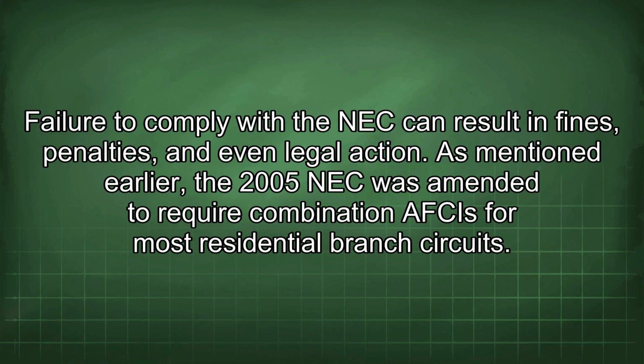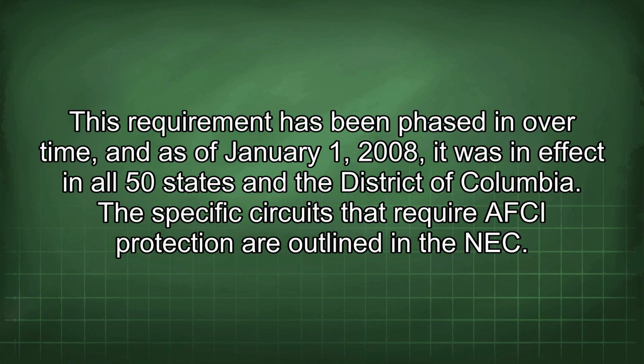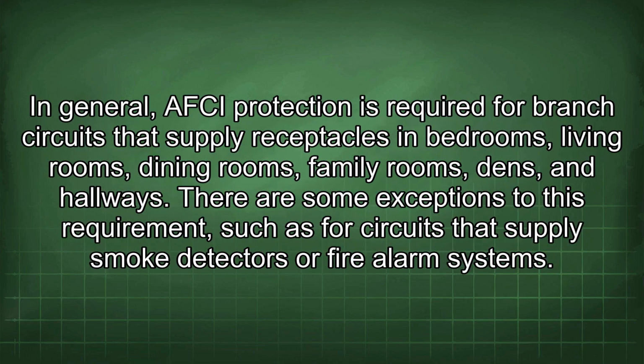As mentioned earlier, the 2005 NEC was amended to require combination AFCIs for most residential branch circuits. This requirement has been phased in over time, and as of January 1, 2008, it was in effect in all 50 states and the District of Columbia. The specific circuits that require AFCI protection are outlined in the NEC. In general, AFCI protection is required for branch circuits that supply receptacles in bedrooms, living rooms, dining rooms, family rooms, dens, and hallways. There are some exceptions to this requirement, such as for circuits that supply smoke detectors or fire alarm systems.